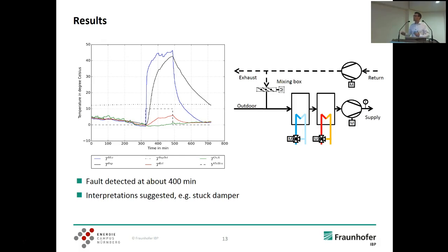For example, this mixing damper here. If we have a closer look, what we can see is that the outdoor temperature goes well below 0 degrees Celsius. And typically in the air handling unit, you have some control strategy applied to avoid freezing of the coil at temperatures below 0 degrees Celsius. So this control logic most probably comes into place here, increasing the temperature of the supply air and the mixed air temperature to prevent freezing of the heating and cooling coil. So detecting a fault is one problem. Isolating and identifying the root cause is a second problem. This will be addressed in future iterations.